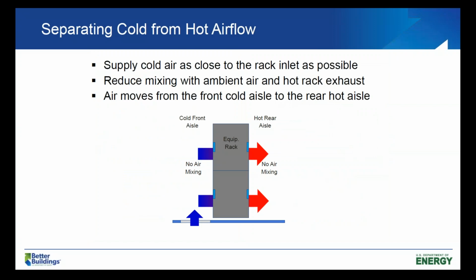So again, the basic concept of good air management is to keep the hot and cold airflow separate, which is exactly the opposite of what one tends to do in normal office space where mixing is a good thing. But here, mixing is a bad thing. And so the ideal is shown in this illustration where the cold air is supplied to the rack. It goes through the rack. It doesn't mix and then it goes back to the cooling equipment. Next slide.